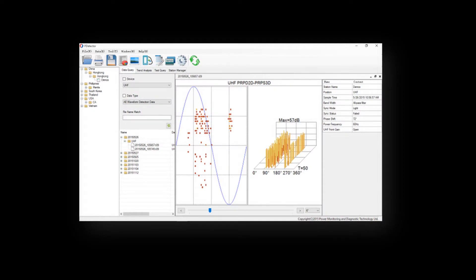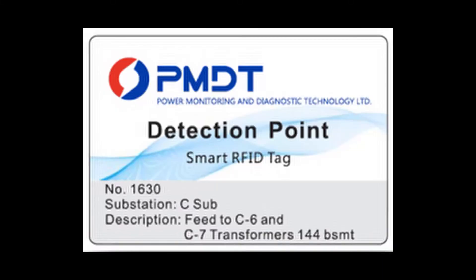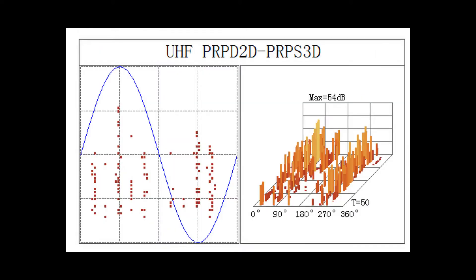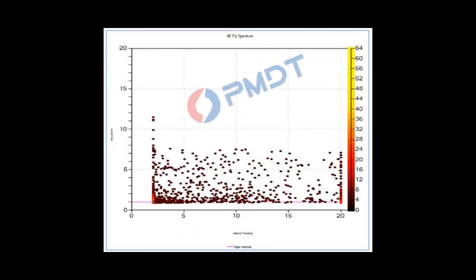The P-Detector features a PC-based data management software with automatic reporting, wireless sensor connection to the UHF and HFCT sensors, power and light frequency sync functions, onboard storage, and RFID asset tagging. Multiple detection modes and data spectrums such as PRPD, PRPS, signal cycle, phase, waveform, and amplitude are used to determine the PD type.